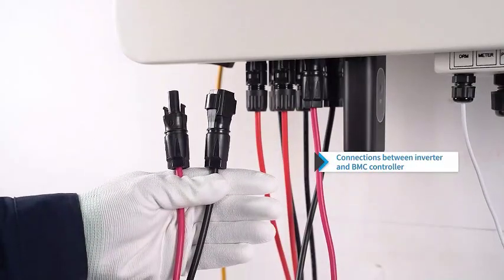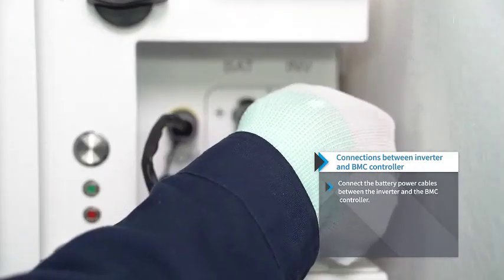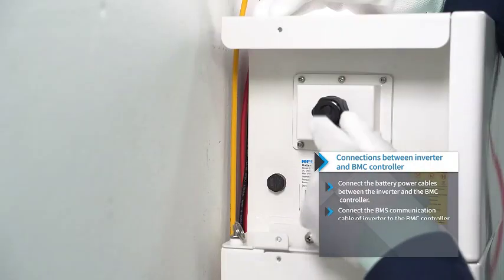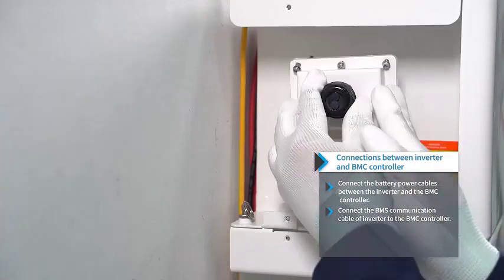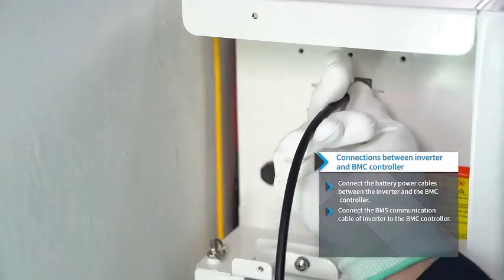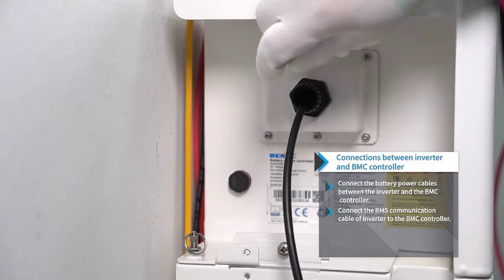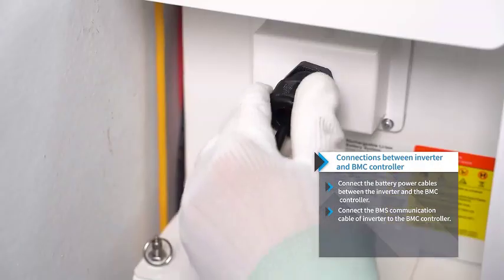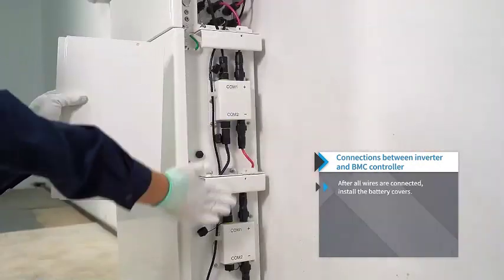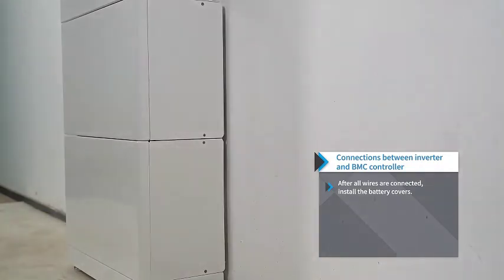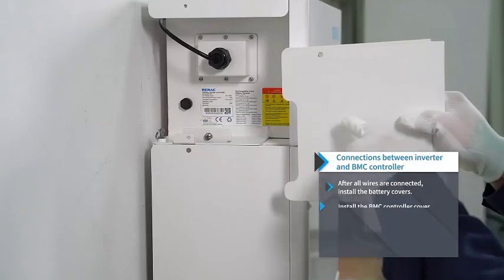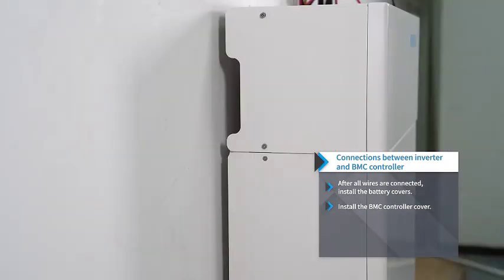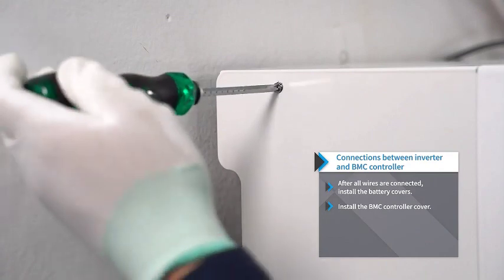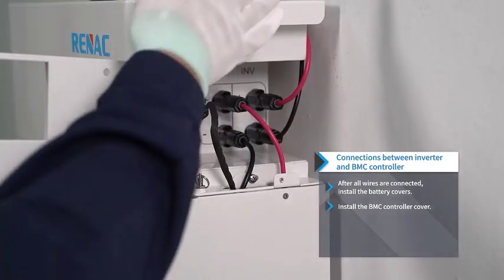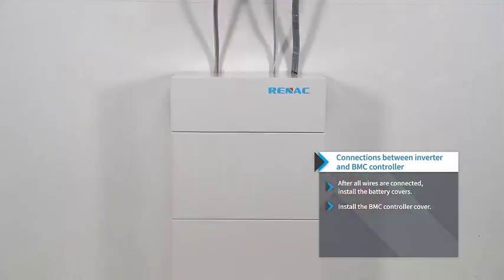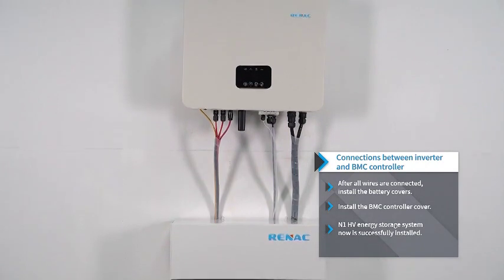Connections between inverter and BMC controller. Connect the battery power cables between the inverter and the BMC controller. Connect the BMS communication cable of the inverter to the BMC controller. After all wires are connected, install the battery covers. Install the BMC controller covers. The N1 HV energy storage system is now successfully installed.